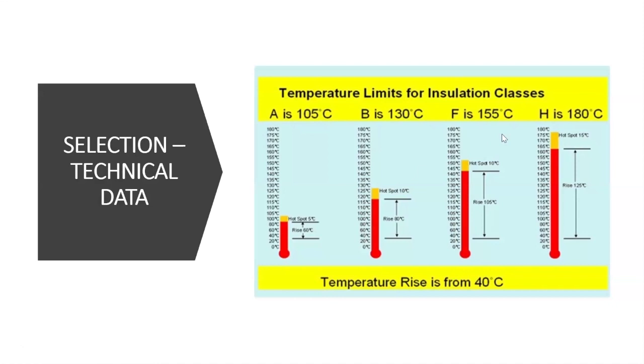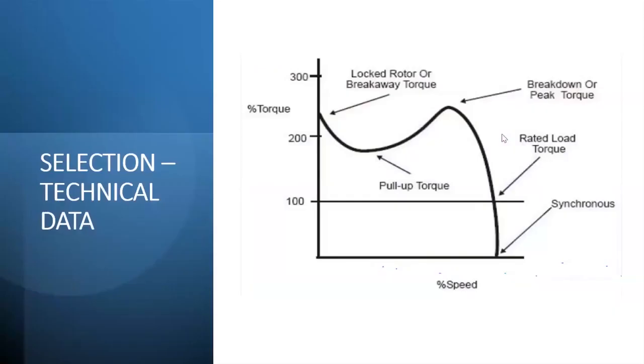So insulation class is very, very important when selecting our motor for our application. And the technical data, every motor and its application is being used for. So when procuring a motor, it's prudent that we ask for the technical data of that motor for us to do our right analysis in the selection of the motor. On the screen is the technical data, which shows the locked rotor or breakaway torque of the motor, the pull-up torque, the breakdown torque, and the rated torque.